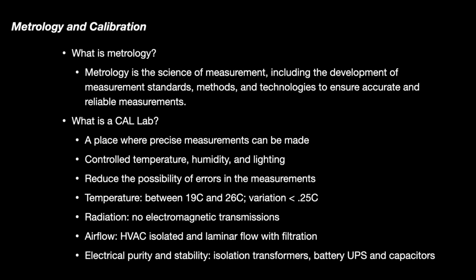For ordinary purposes, having a constant temperature is better than having a cold temperature or a hot temperature. But somewhere in the range of 19 to 26 Celsius is good enough as long as it's stable. Obviously, you don't want electronic radiation because that gets picked up on the wires, and then that's back into the voltmeter, and you've got spikes all over the place.